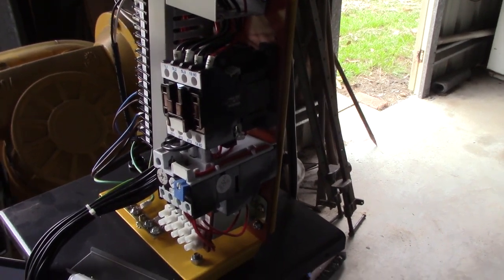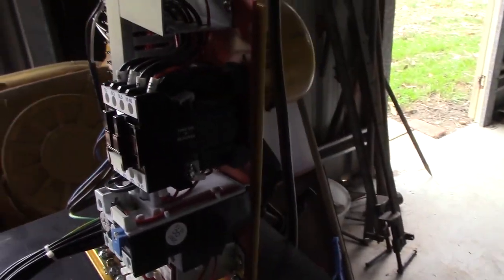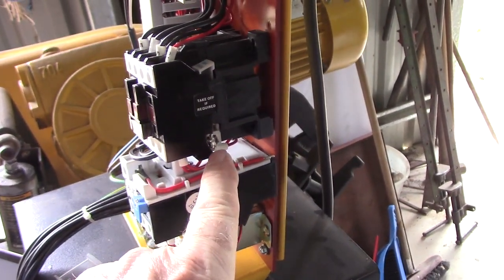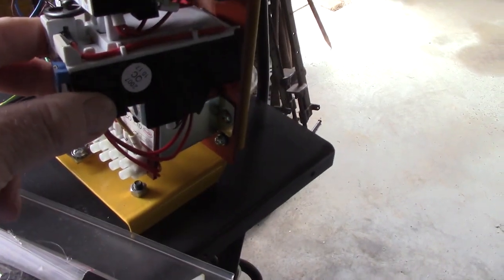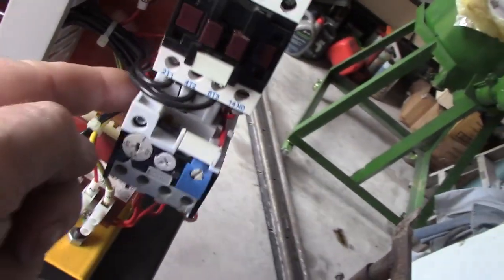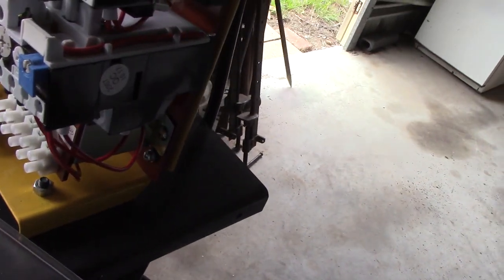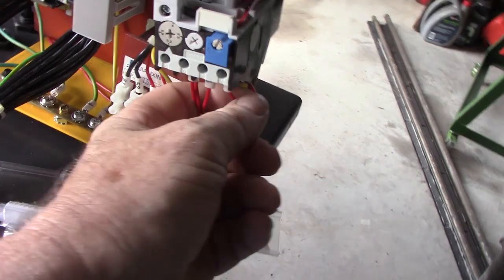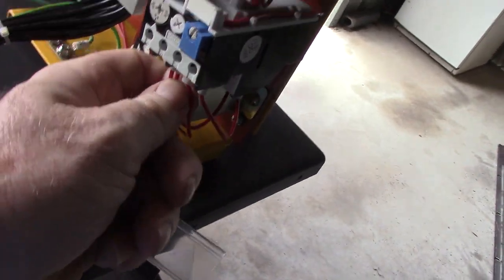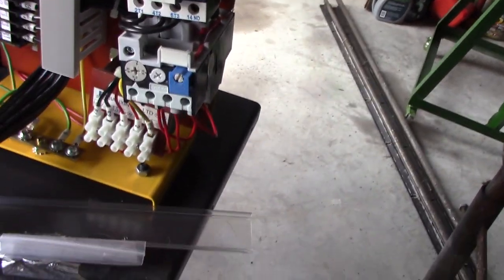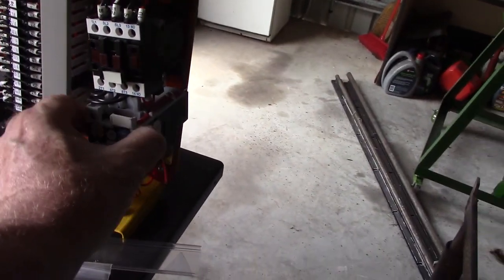I found out a little bit about this switch now. I've had to play around with it with power to do some testing. I've got the power off again now so I can trace some wires through. This here on the back and that one diagonally opposite on the other side control the solenoid. And I can't find any power going into them. This is a thermal overload, isolated on it. So it could well be that something has gone wrong in there and it's not working. I'm just going to do a little bit more testing, just probe around and see where these wires come from, just to confirm that it is in fact this unit that's causing me the problems.